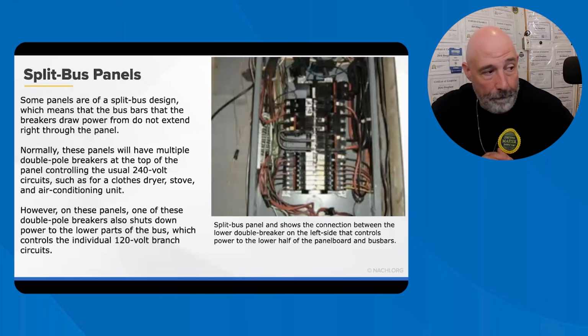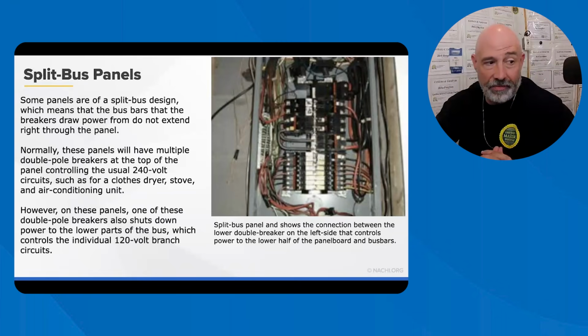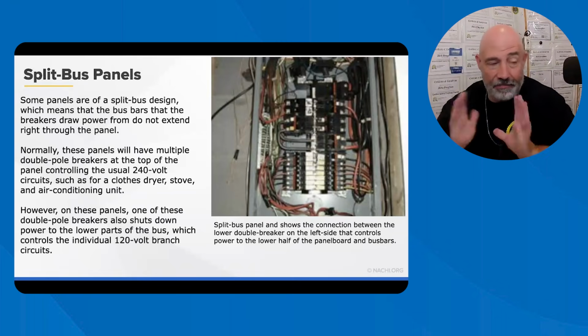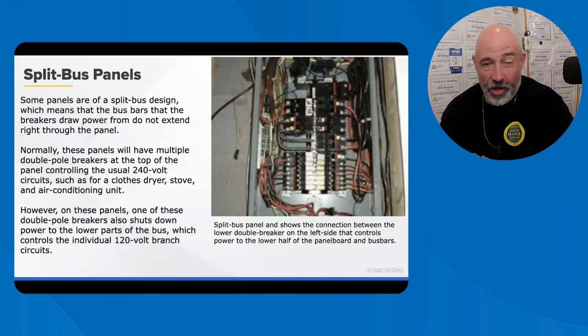Here we got the split bus panels. And so there's two different buses on this panel board or the panel. And you don't see these too often, but a lot of times, if I see something like this, I just say further evaluation from an electrician. The split bus panel is just different. I've seen one or two, I think, in the 4,000 plus inspections I've done. So they're not very common, but you will see them every once in a while.